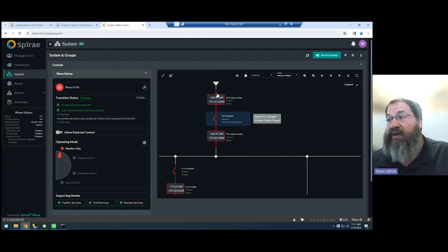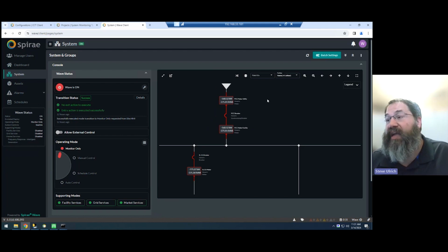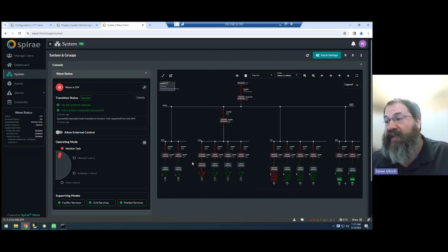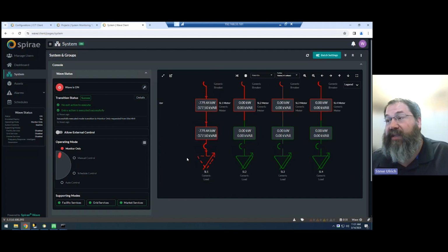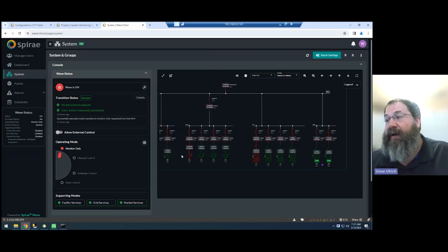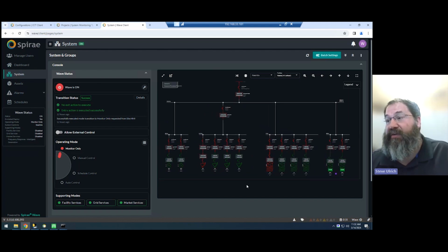So you can see we're currently importing about 568 kW to support our load. The load right now is a relatively good size, 780 kW is currently in place. And we have one PV that's currently online. Like I said, we have the ability to extend this out for additional assets if we need to. But currently the ones that are online is just one load and one PV.